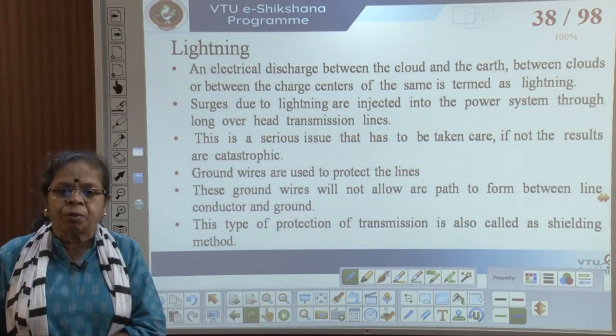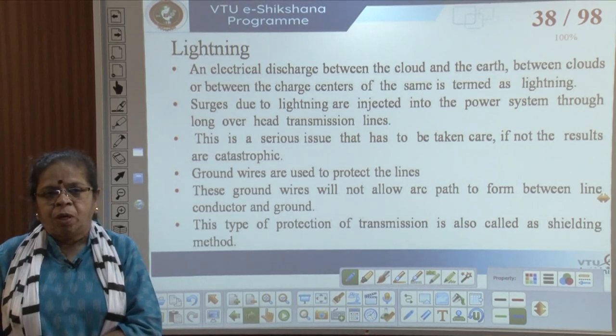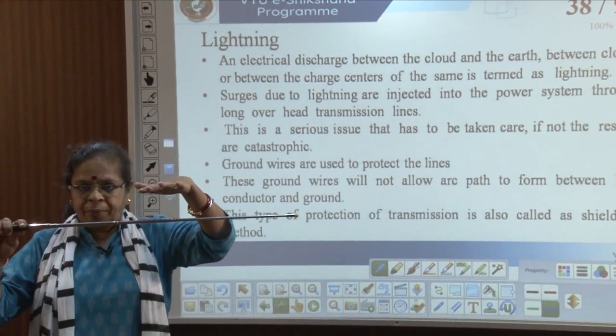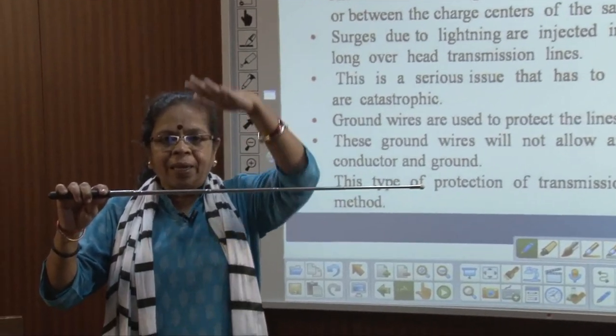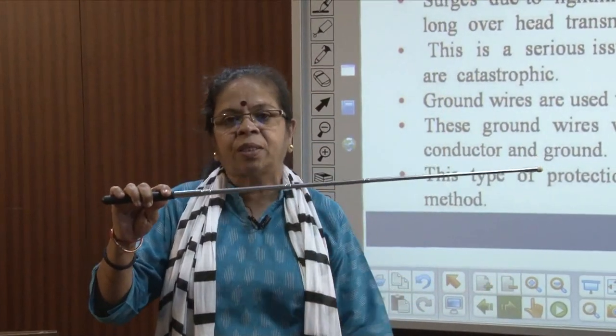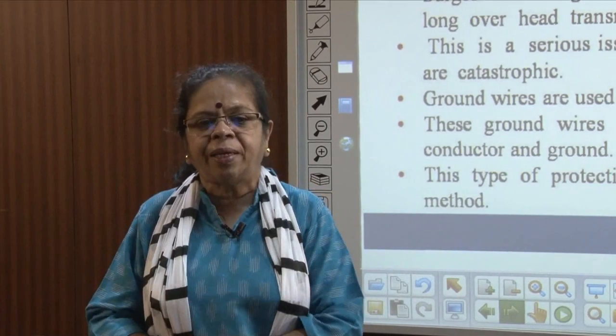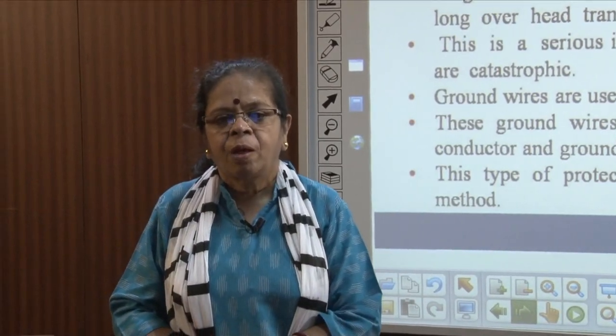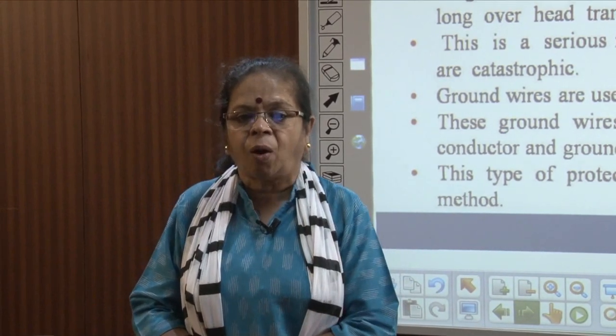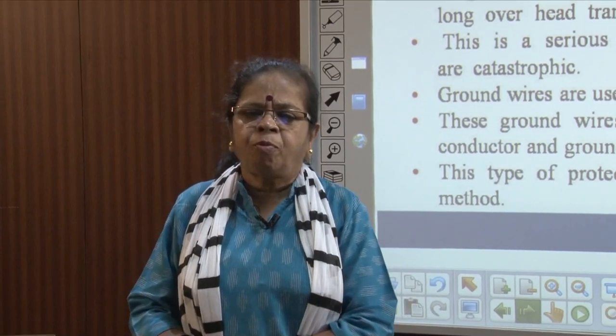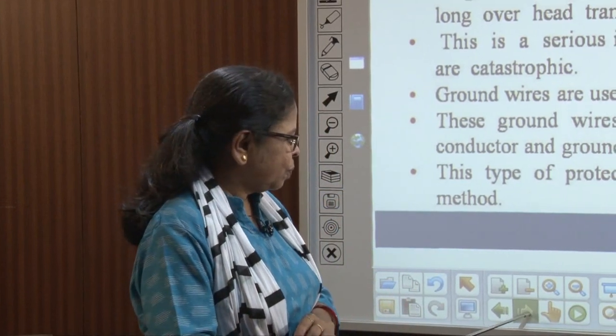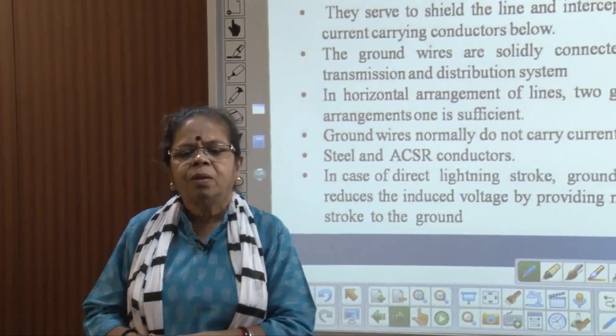Ground wires are provided to protect the lines. If I have a transmission line conductor, I will have a ground wire above it so that lightning strikes the ground wire instead. The ground wire is connected to ground, so the discharge is grounded and the lines are protected. These ground wires will not allow a path to form between the line conductor and the ground — this type of protection is called the shielding method.